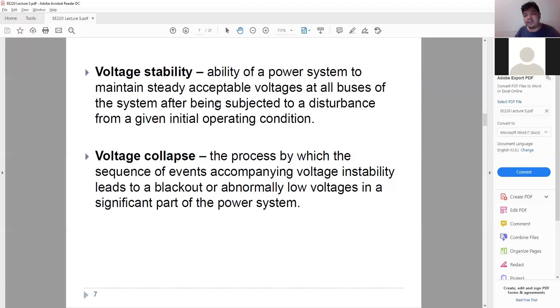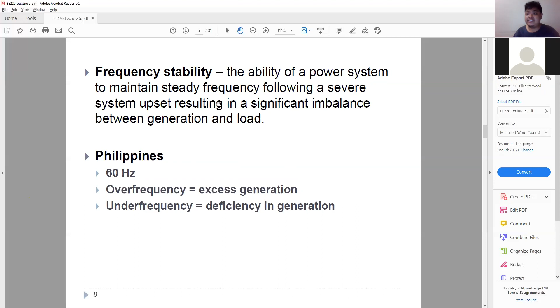For frequency stability, the ability of a power system to maintain steady frequency following a severe system upset resulting in a significant imbalance between generation and load. So our reference is load. If generation is higher than load, that's called over frequency, meaning excess generation. If generation is lower or deficit, that's under frequency. So our reference point is the load.